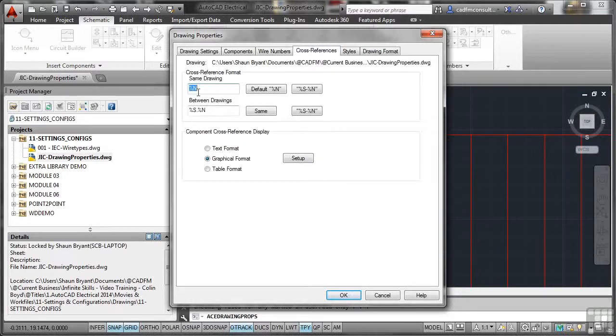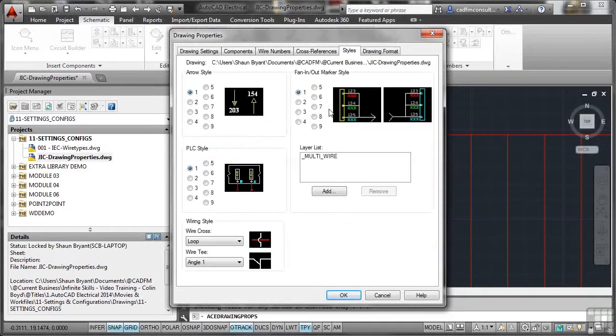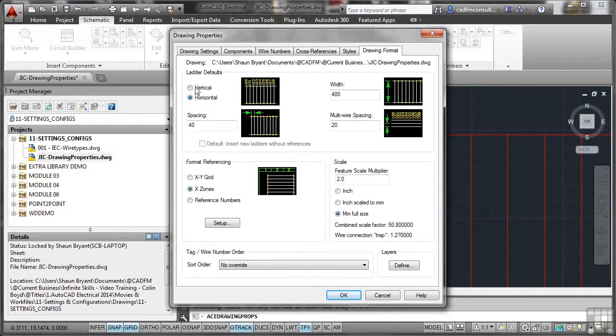Cross-referencing settings: for the same drawing you've got the drawing number; between drawings you've got %S and %N. You can set default button settings and component cross-reference display — graphical, text, or table format. Under styles you've got arrow styles, PLC styles, wiring styles, and fan-in and fan-out marker styles — I rarely change any of that and tend to use the defaults. Under drawing format, when placing a ladder it can be vertical or horizontal by default, with width, multi-wire spacing, format referencing, and scaling. You can set it all as a default in your drawing. I'll OK that now — it updates.